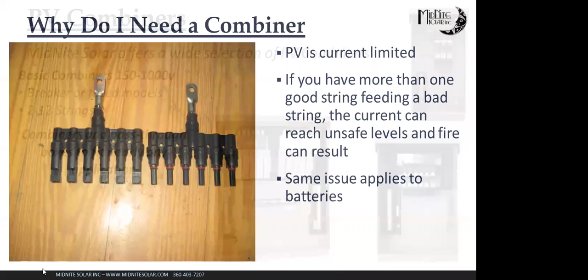And we talked a little about why you need the combiners, but I left this slide in here. You need to know what you need for a combiner. We have almost anything you could want for combiners. If we don't have it, Alti can tell you who else makes it and get it for you. You can use them as pass-through boxes. You can use them as load centers. Some of them can be reconfigured for, like the one on the left there, 5 strings into one inverter and 5 into another. But we have things from 150 volts all the way to 1,000, 2 strings all the way to 12 strings. So don't be afraid to reach out to us when you're getting into combiner selection if you have any questions. But again, just make sure that it does what you need it to do, voltage and current wise. And then also make sure it'll do enough strings.